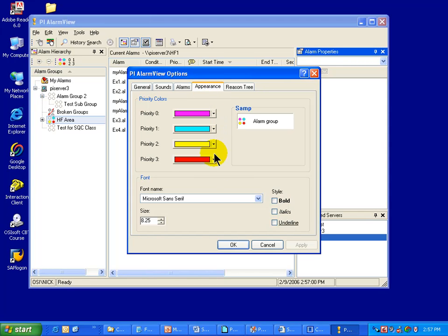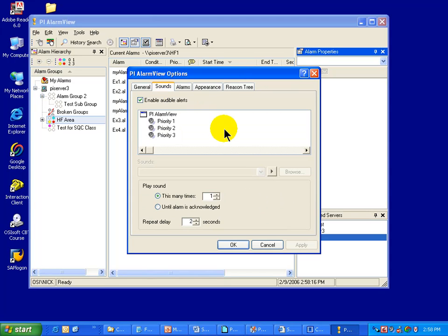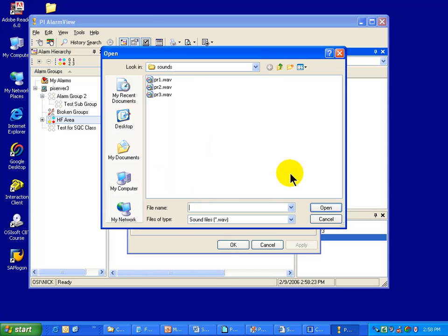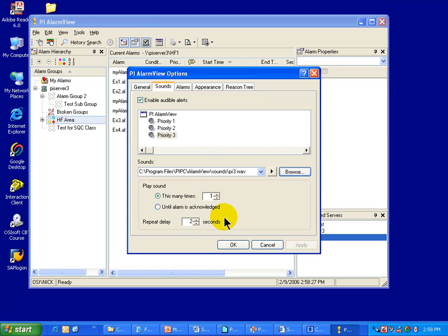This is where you can set the priorities. We also have a Priority 0, which is for an alarm that has not been specifically assigned a priority. In addition, you'll notice that you can configure sounds to go with these alarms. Here are the different priorities and the corresponding WAV files. You can browse for WAV files and control how many times the sound plays, whether it plays until acknowledged, etc.